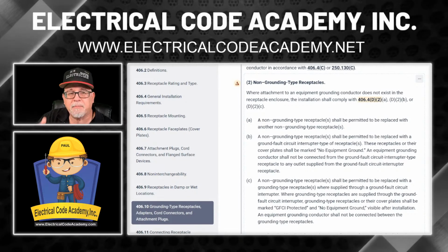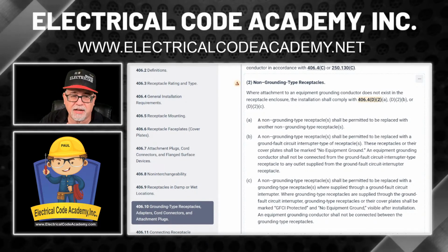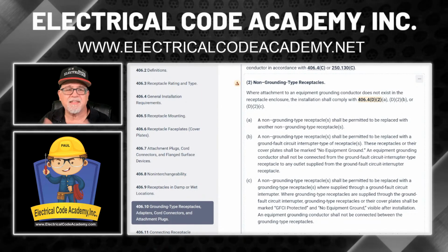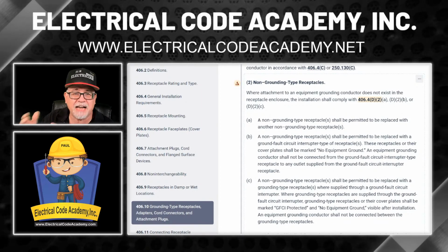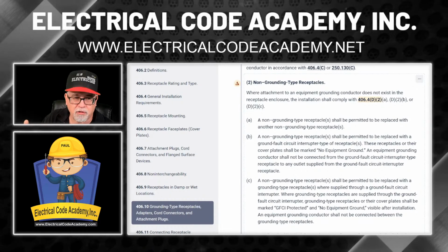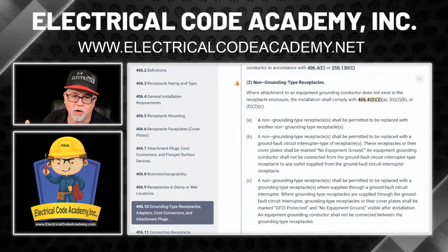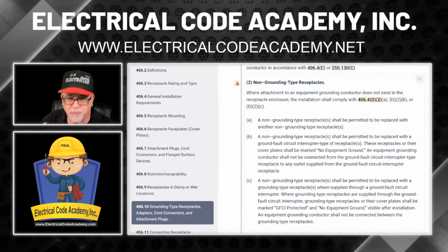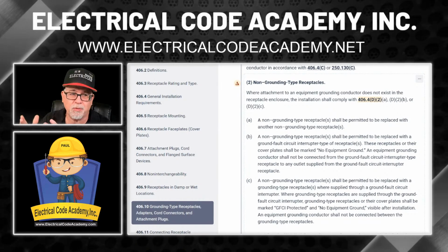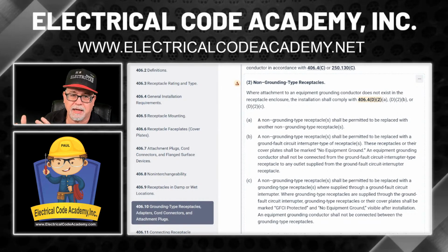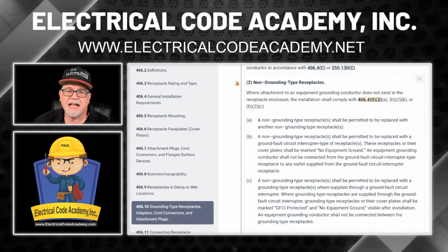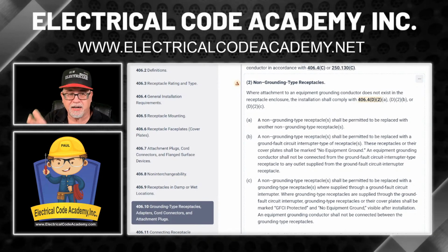So connecting anything beyond that to the green screw on it and going downstream to other receptacles would be misleading and it would be false because you're not going to be establishing an equipment ground, an effective low impedance ground fault current path. You're not going to be establishing it from the GFCI. It wasn't there to begin with, so you're just not going to use it, okay? All right, so that's what he did, and he stopped right here.